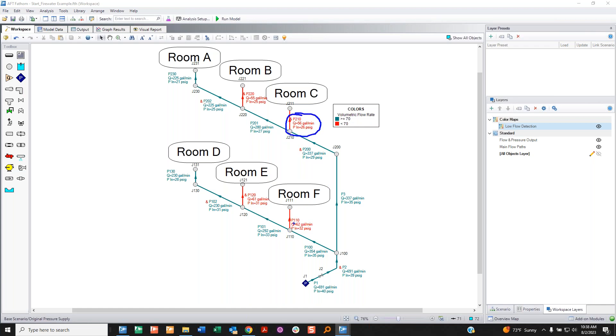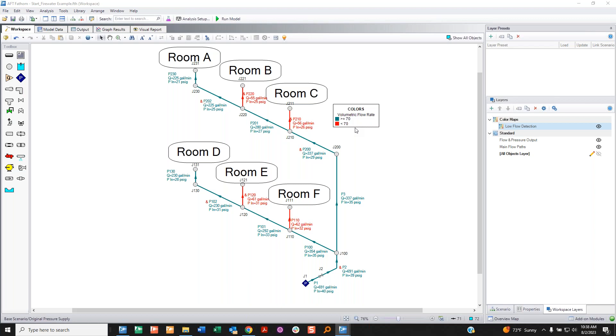With the color map layer on, any pipe that had lower than 70 gallons per minute is red — which happens to be four out of our six rooms. Everything else is green because it's all above 70. The story of this model: I have a flow rate I need to meet for these rooms and I'm not meeting it for four of them. The color map lets me see the problems easily — I can see right where my problem exists.